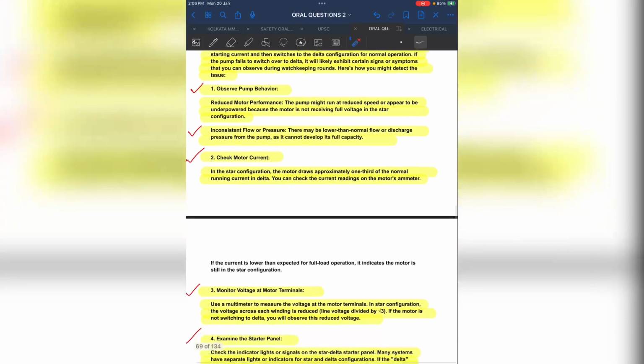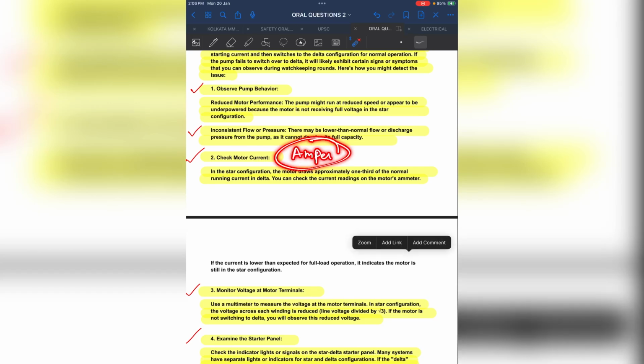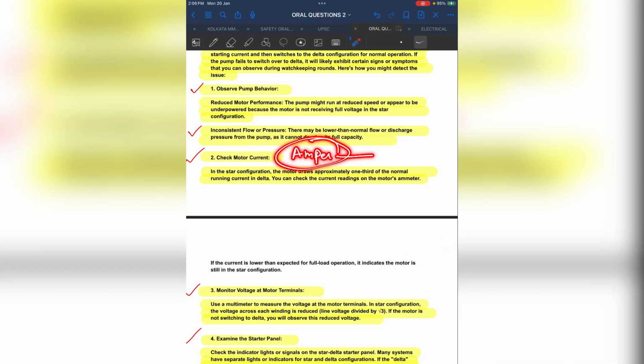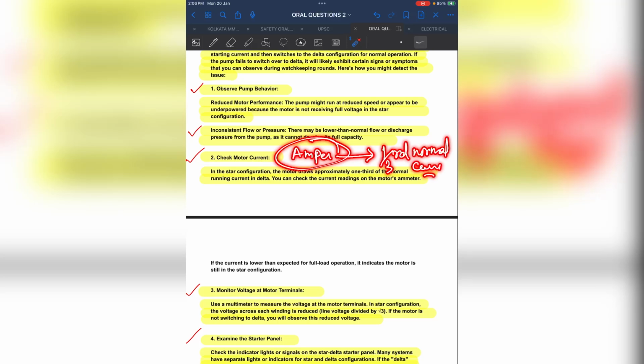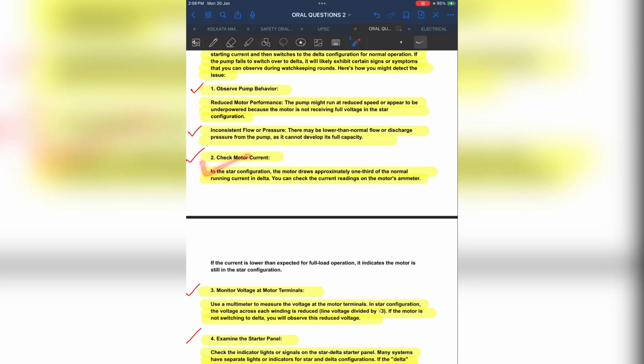So with the help of current, when you see the ampere meter on the terminal and the pump did not switch over from star to delta, you will see your ampere will be less. Ampere will be about 1/3 of your normal running current. So you can observe your ampere will be less. Your motor performance will also be less, because now the motor is running on a low voltage. If there is a low voltage, motor RPM will be slow. It means motor RPM will not be according to your rated RPM. So you can observe the motor performance also.